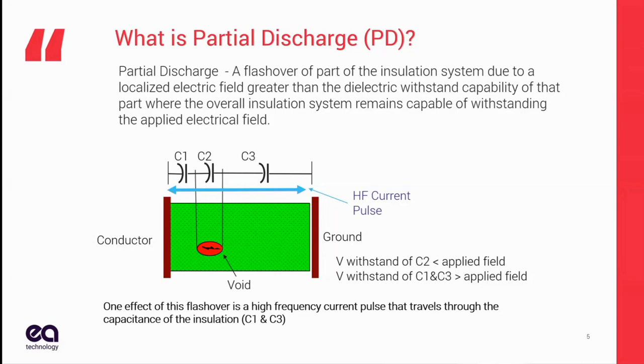There can be some ringing at the end, but it's largely unipolar. So that is the science of partial discharge. It's a real current. It can be measured. It follows Ohm's law. It wants to find a path to ground. It is not voodoo or black magic. It is real, and that's what we're going to focus on today.